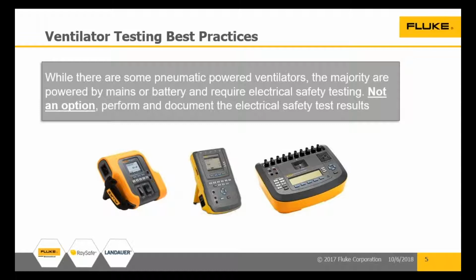Okay, so safety standards, especially electrical safety: any electromedical device, whether it plugs into the wall or whether it has an internal power supply, usually that means a battery, has to have an electrical safety test. Here's what NFPA 99 says. See if you agree with me. Because there's been a few changes since 2011. NFPA 99 now says you must test and make measurements on incoming inspection of a medical device, and after any repair in which you open the enclosure of the medical device.